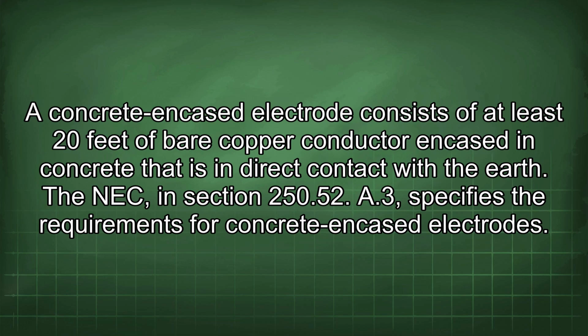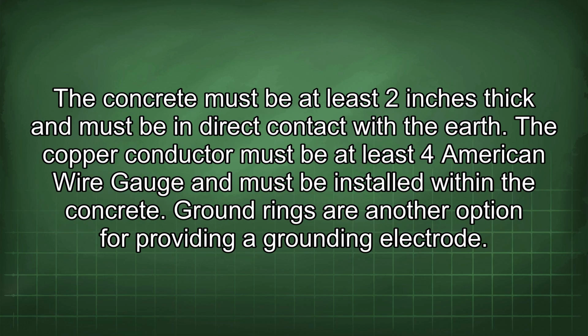A concrete encased electrode consists of at least 20 feet of bare copper conductor encased in concrete that is in direct contact with the earth. The NEC in section 250.52(A)(3) specifies the requirements for concrete encased electrodes. The concrete must be at least 2 inches thick and must be in direct contact with the earth. The copper conductor must be at least 4 American wire gauge and must be installed within the concrete.